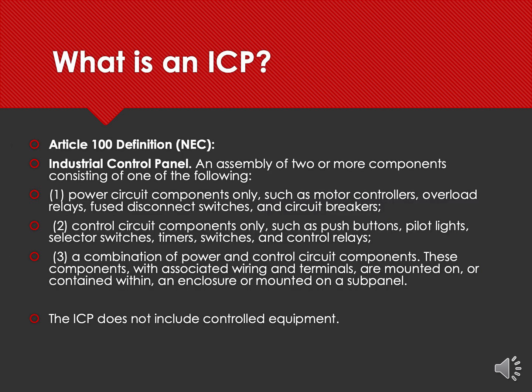In terms of what actually is an industrial control panel or what it includes, this can be found in section 409.2 of the National Electrical Code. As you can see by looking at the words on the slide, it's an assembly of two or more components. Almost always it includes both a power circuit and a control circuit. Under the power circuit umbrella, we are talking primarily about things like motor controllers and overload relays and fuse disconnects and the like. These are the things that actually provide power to the actual equipment, as the name suggests.